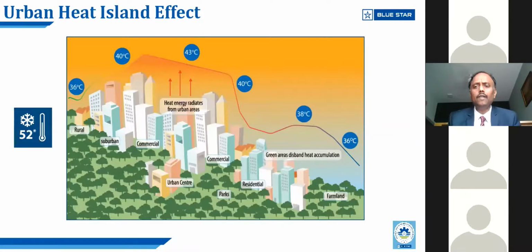For example, if the outside ambient in Chennai is 38 or 39, when you go to the terrace and monitor the temperature, it will be 41, 42, or even 43 degrees centigrade. This phenomenon is called urban heat effect, arising out of global warming. Temperatures are rising due to global warming, and an additional 2 to 3 degrees is added due to urban heat effect in cities. You have to keep this in mind when designing the air conditioning system of buildings.